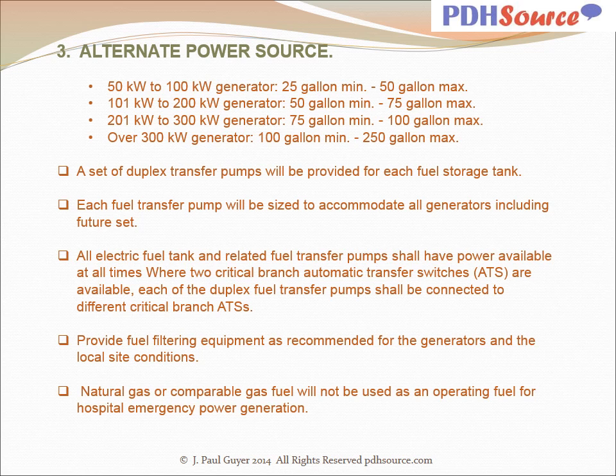A set of duplex transfer pumps will be provided for each fuel storage tank. Each fuel transfer pump will be sized to accommodate all generators, including future sets. All electric fuel tank and related fuel transfer pumps shall have power available at all times. Where two critical branch automatic transfer switches are available, each of the duplex fuel transfer pumps shall be connected to different critical branch ATSs. Provide fuel filtering equipment as recommended for the generators and the local site conditions. Natural gas or comparable gas fuel will not be used as an operating fuel for hospital emergency power generation.